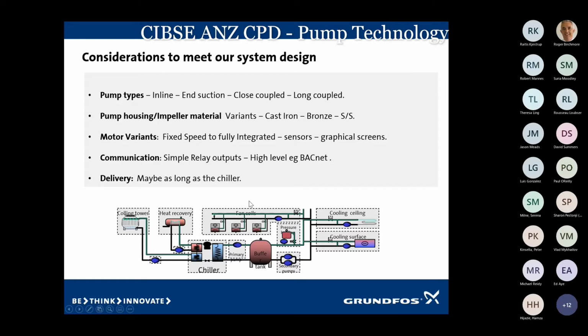Some of the considerations when we're designing our systems include the pump types, whether we go inline or end suction, close coupled or long coupled, depending on the configuration of the pipework. Then the pump housing and the impeller material. If it's a closed loop system, heating and cooling, then cast iron impellers are fine. But for cooling tower and domestic hot water, we must use a stainless steel or a bronze impeller, just to avoid any corrosion in the water.